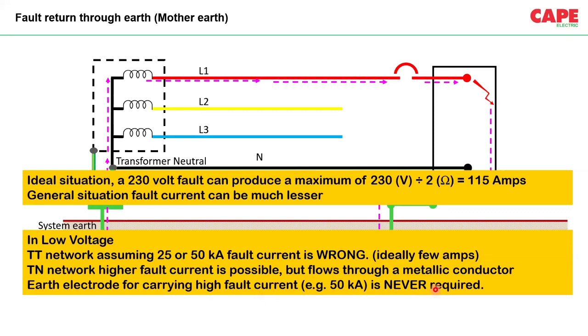Why I made this statement is nowadays, if we look at the specification of the electrical requirement, most of the time, chemical earth electrode with 50 kiloampere fault current is requested by the industry for application in low voltage. This is never going to happen. Please note that you don't need it.